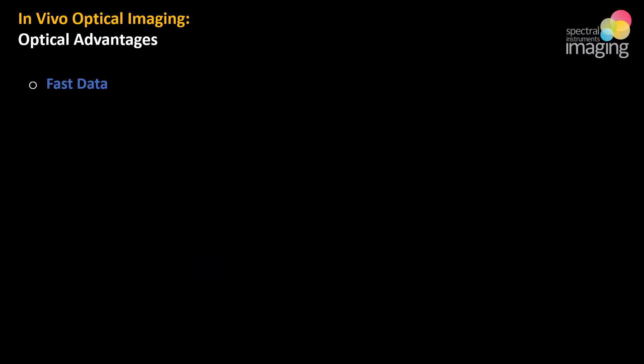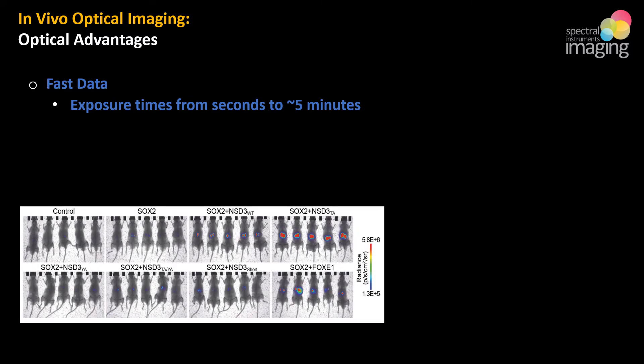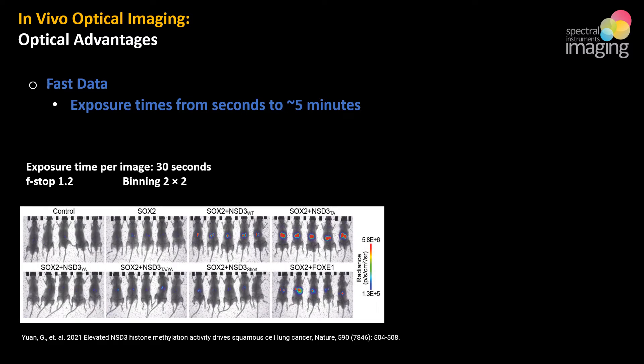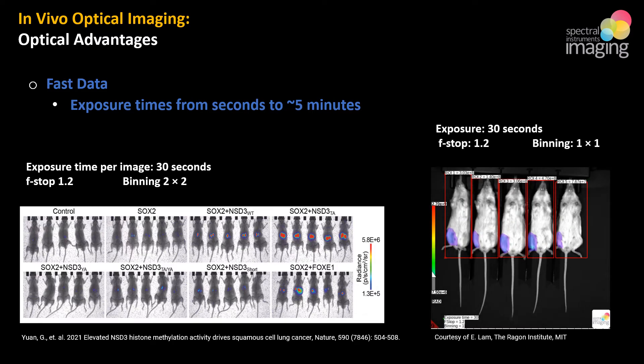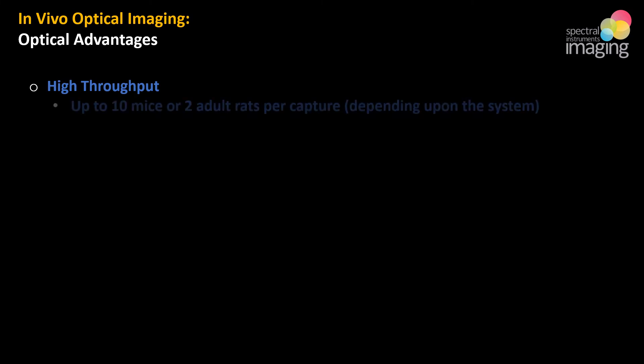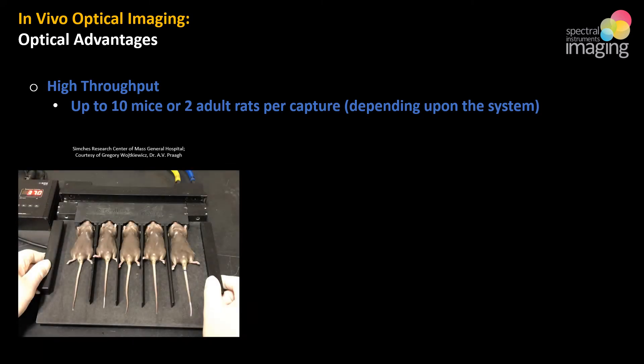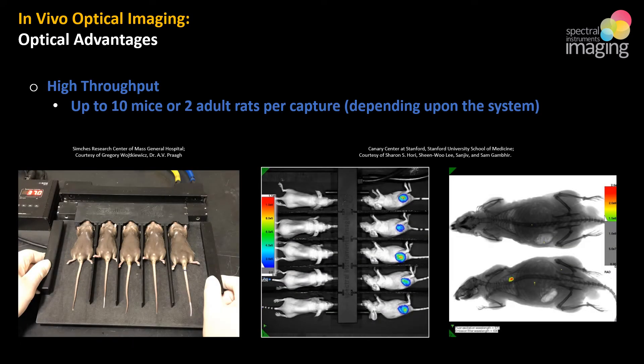The next advantage of optical over other modalities is fast data. Acquisition times from bioluminescence and fluorescence imaging range from half a second up to five minutes, typically between 30 and 60 seconds. Below, a series of acquisitions from a pure capture perspective took only four minutes of exposure total for 40 data points. Here's another acquisition of five mice with five data points using just 30 seconds of exposure time — in clear contrast to other modalities, which can require acquisitions from roughly one to 30 minutes. Another advantage is high model throughput: optical imaging systems can rapidly capture data from five mice, with some able to handle up to ten mice at one time or two adult rats.